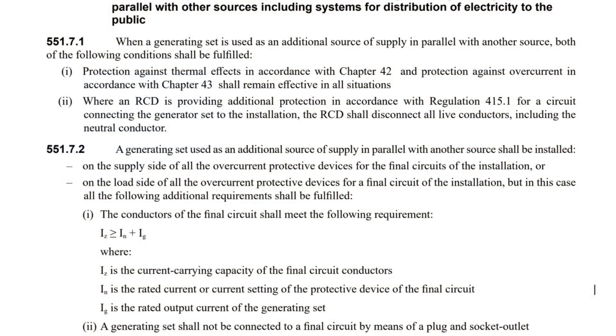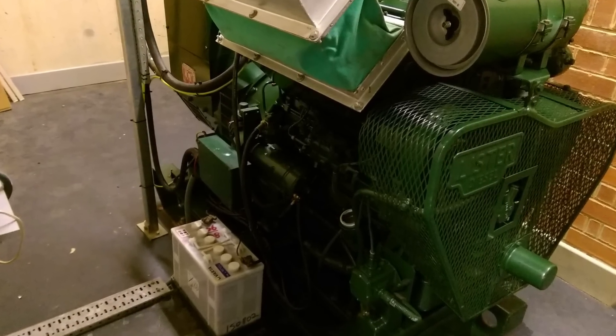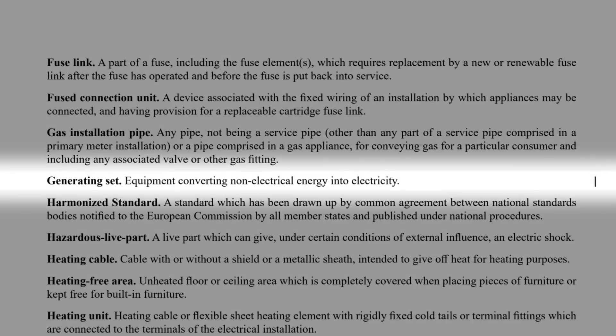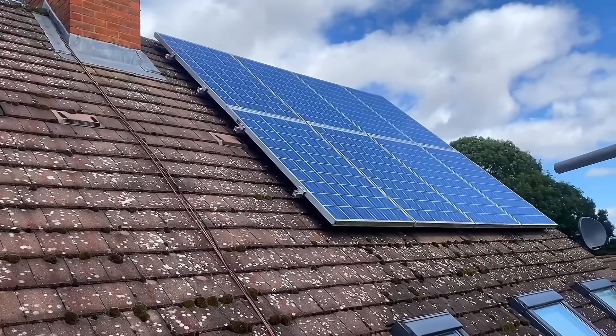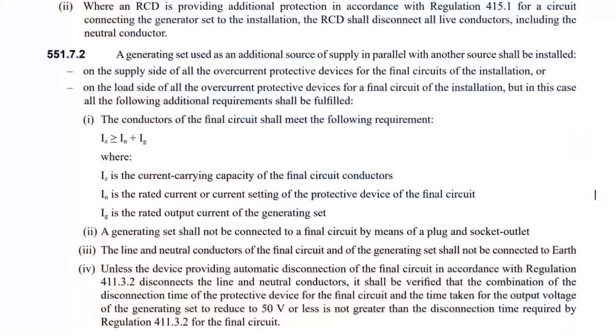One of these is in BS 7671 regulation 551.7.2. This regulation is in the section that speaks about generating sets. Now the temptation is to think of that as something like a diesel powered generator used for backing up a hospital. However, in the definition section of the regs, a generating set is simply defined as equipment converting non-electrical energy into electricity. So a solar PV array of panels would definitely be classed as a generating set. The regulation we're interested in is 551.7.2, which is quite a lengthy one, so we're going to pick out the parts relevant to this video.